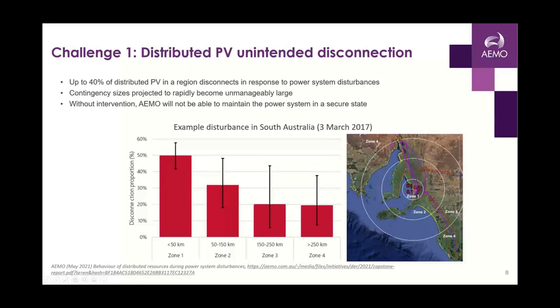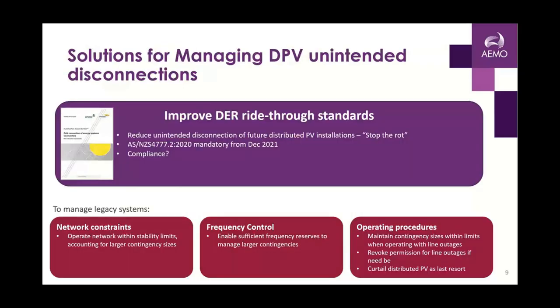So this means that we might have really large contingency sizes. When we have an event, we have to not only worry about the size of the loss of a potential generator, we also have to think about the loss of the PV additional to that generator. And that would mean that we have to do a lot to manage that.